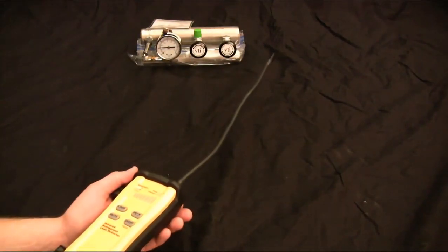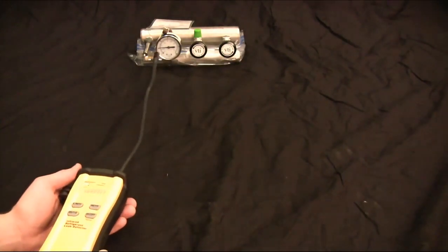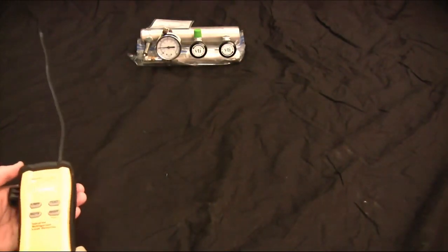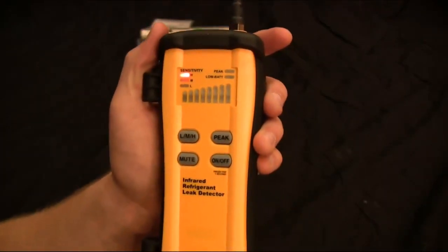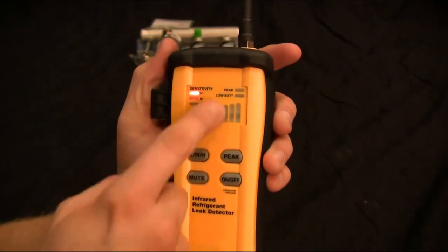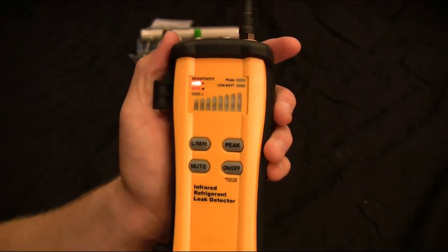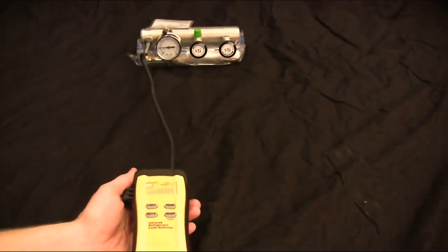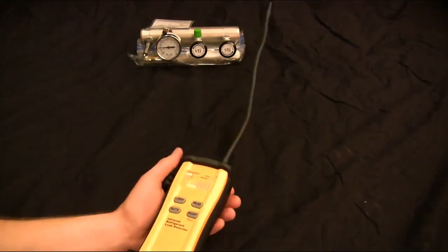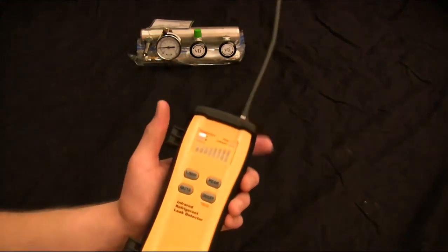Alright, let's just sweep over this. Now see, even at .05, the high sensitivity is still going to sense it. But you can see that it doesn't go all the way up on the bar graph. I think it just made it out of the yellow on the bar graph. So it went up about five or six spaces. So it's not as big as the leak that we were sensing before.